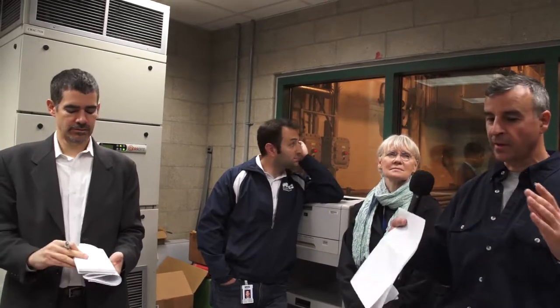Do we need to do extra cleaning? We certainly do. We have it on a timed basis, every 3 months or so. I have to vactor out the wet well. I have to vactor out the tanks. But it's only a preventative measure. It's not something that needs to be done to keep the facility in operation.